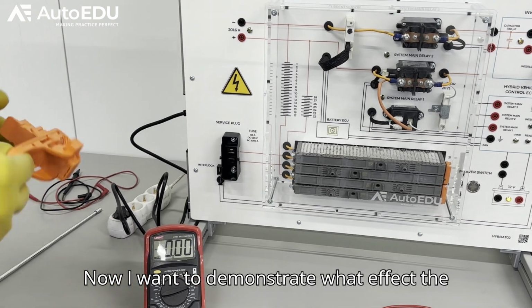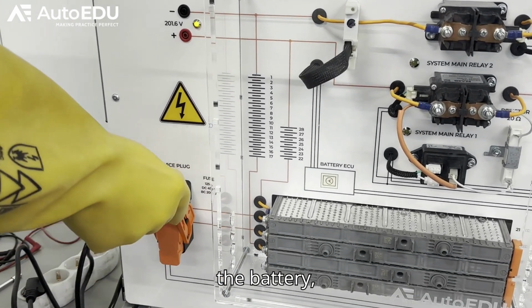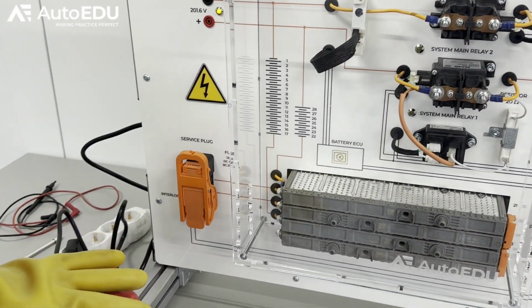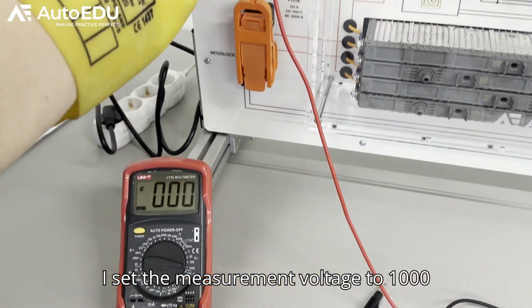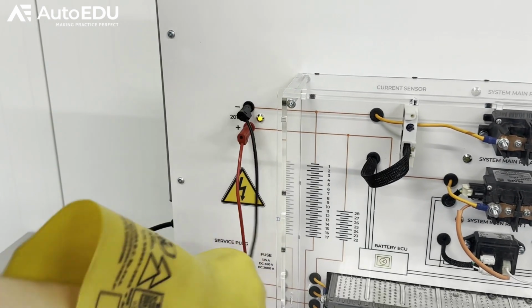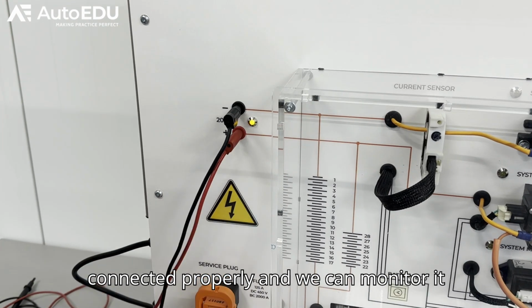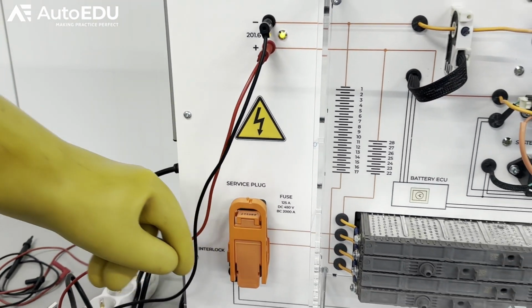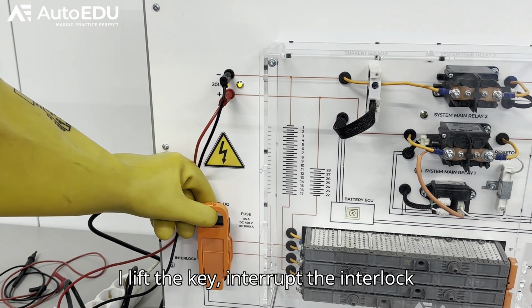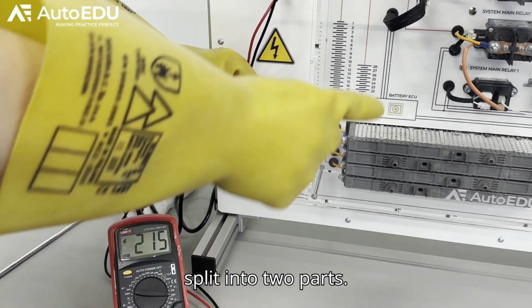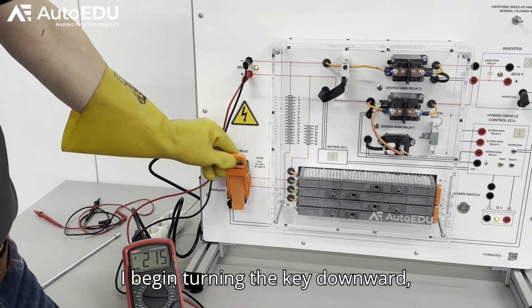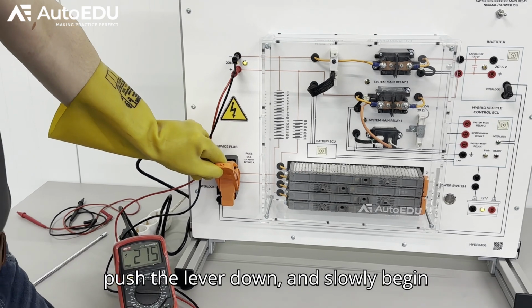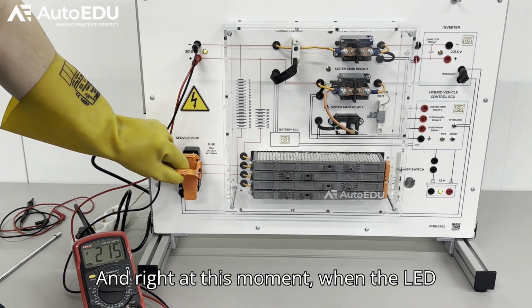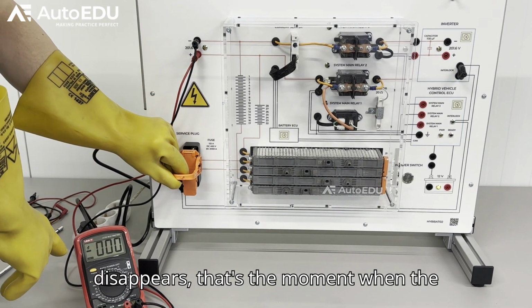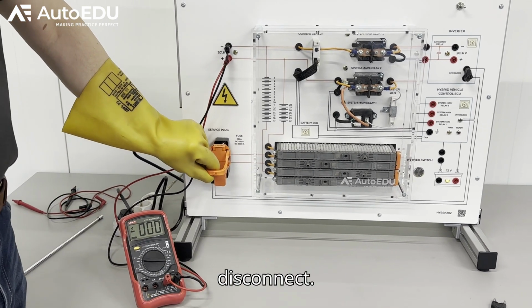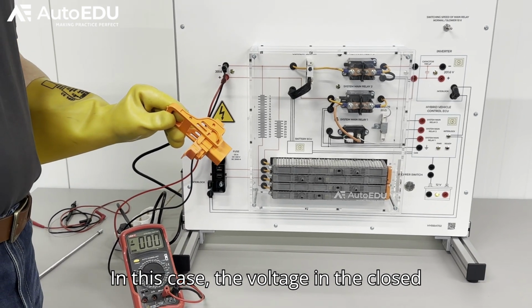Now, I want to demonstrate what effect the key has and when it affects high voltage inside the battery. I set the measurement voltage to 1000 volts. We see that it's lit. The LED shows that these contacts are connected properly, and we can monitor it slowly. I lift the key, interrupt the interlock circuit, but the battery hasn't yet been split into two parts. I begin turning the key downward, push the lever down, and slowly begin pulling out the contacts, and right at this moment, when the LED goes out and you see the voltage disappears, that's the moment when the main power contacts in the service key disconnect. In this case, the voltage in the closed battery circuit is gone.